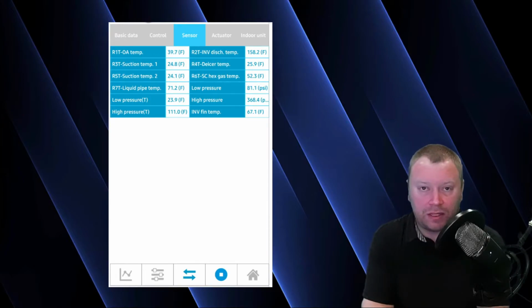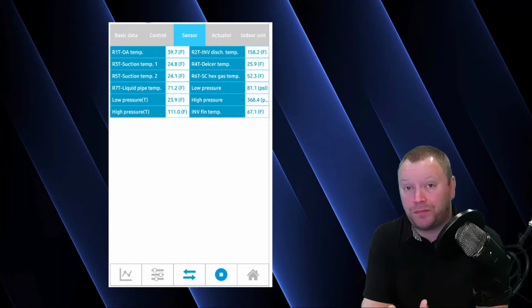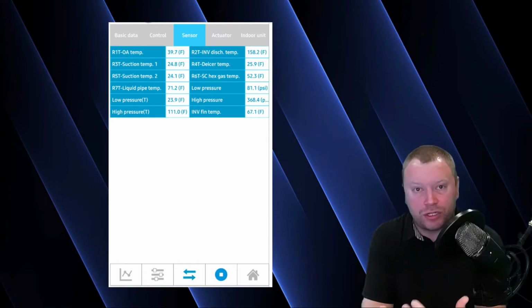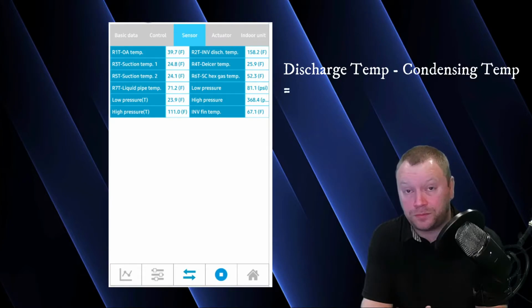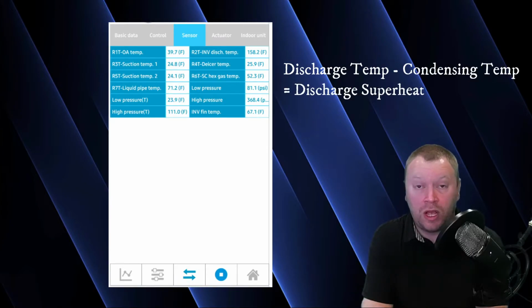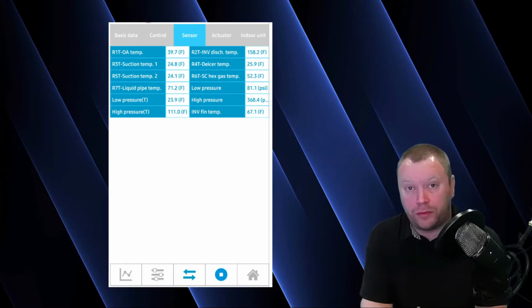Now, as we discussed in the last video, the method that I typically use is always start with the compressor. The compressor discharge pipe temperature is always the hottest point in the system, or it should be anyways. And we like to look at what our discharge superheat is right off the compressor, which gives us a baseline for how the compressor is running. And what we'll do here is we'll take our inverter discharge pipe temperature, subtract the condensing temperature, and that difference is our discharge superheat. Now, that value, depending on the load, depending on the conditions, should be anywhere from 30 to 80 degrees.